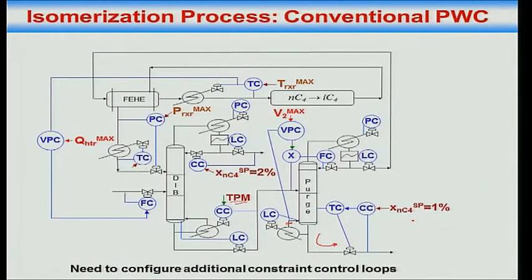So what do I do? I'll say, okay, I'll measure the boil up and I'll adjust the ratio set point so that the boil up is close to max but not max. Note here that there will have to be some amount of back off in the set point, minus delta. I have put in here max, but this will also have to have some back off minus delta, because I cannot afford to lose reactor temperature control.